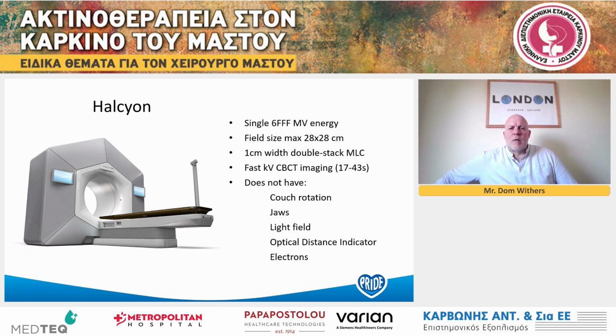The MLC is double stacked. They are 1 centimeter wide leaves, but they are offset. So the aperture has a resolution of 0.5 centimeter, similar to the Varian Millennium MLC, or the Elekta Agility MLC. All imaging is done with cone beam. There is no planar imaging for kV, but it is very fast. Because it is enclosed inside the bore, there is no speed limit for the gantry to move round, and a complete cone beam can be obtained in as little as 17 seconds. And in fact, the breast scanning protocol is about the shortest, and that is the one that is 17 seconds. It is also the lowest dose protocol of all the imaging.